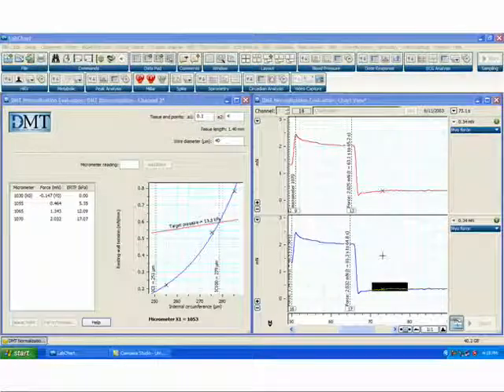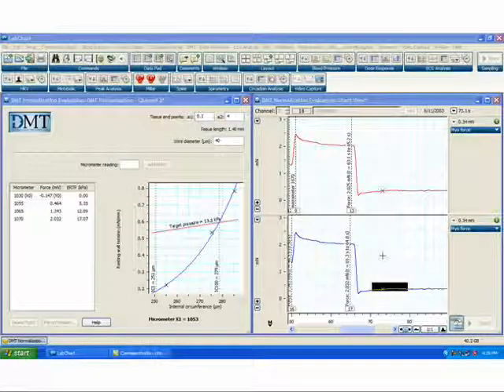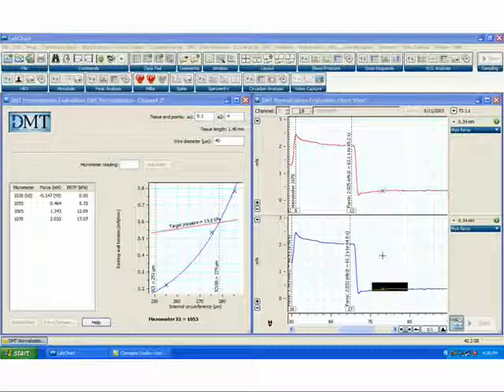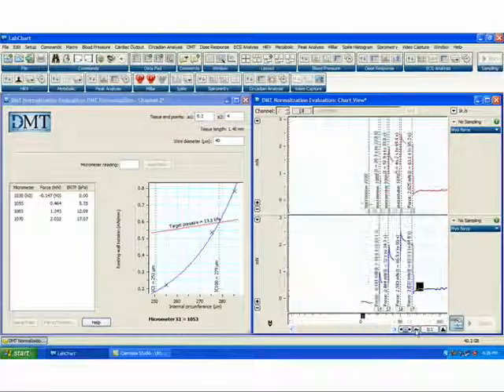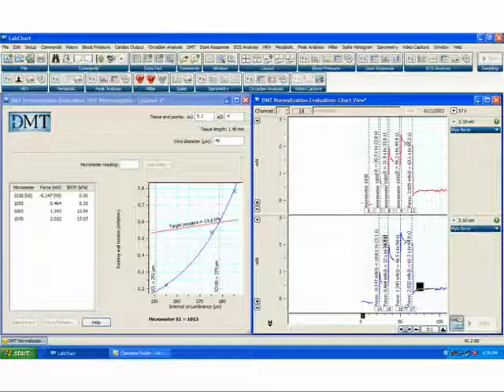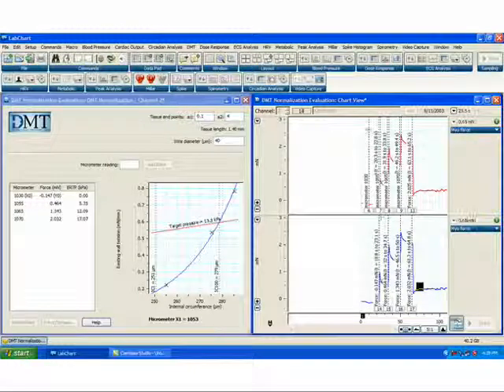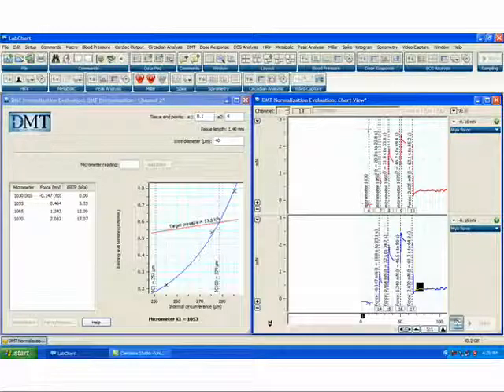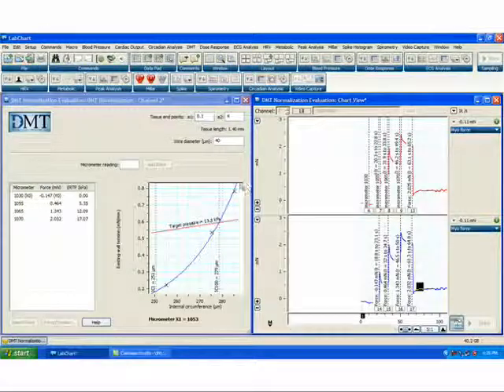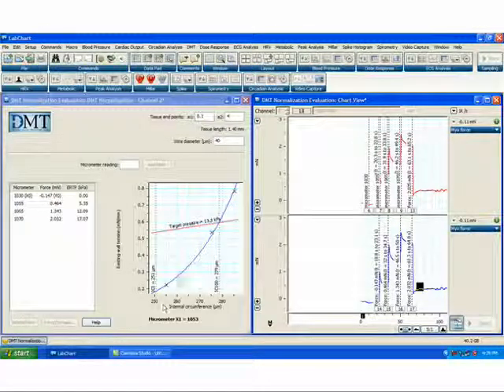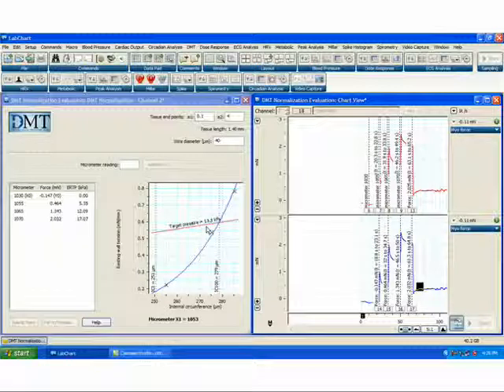Overall, the DMT normalization module will help you save time during acquisition. In the past, researchers were forced to export this data into third-party software in order to plot this curve and calculate the micrometer setting at which the target pressure of 13.3 kilopascals would be reached.